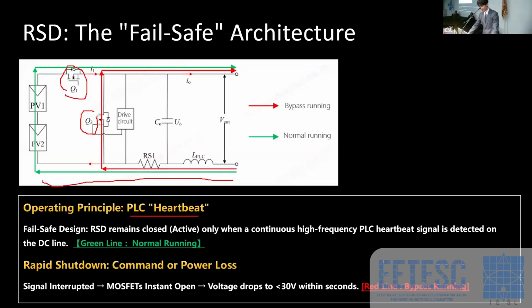The inverter or the central controller sends the high frequency signal through the existing DC cables. As long as the rapid shutdown unit feels its heartbeat, the system keeps running. But here is the beauty of the safety logic. The moment the signal disappears, whether because someone pushed the emergency button, or the AC grid failed, or even the cable was cut by the fire, the rapid shutdown units will perform a fail-safe shutdown instantly. The real engineering achievement here, as we discussed, is our dual modulation circuit. It's designed to filter out the heavy noise of a solar system to ensure that the heartbeat is never lost. So this is how our rapid shutdown works.